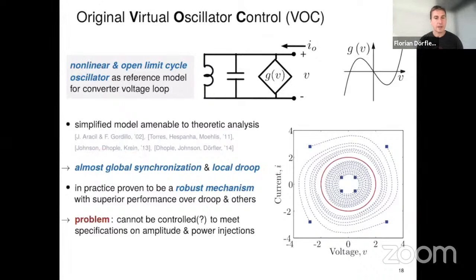With a simplified model, you can analyze and prove many nice properties — locally it reduces to droop control, and you can prove almost global synchronization when the oscillators are all coupled, and so on. In practice this has proven very robust, but it's really hard to control these things. They would synchronize, but often to something you don't want — they're too robust for their own good. Telling them to synchronize to a specific amplitude, with specific relative phase angles, is very hard to achieve with nonlinear relaxation oscillators.